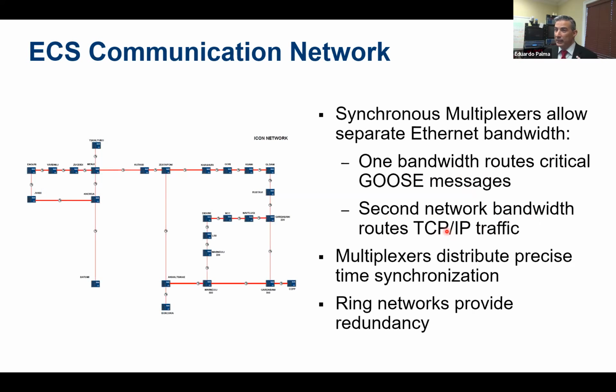Notice that on the physical network, or how these multiplexer boxes are connected to each other, there is one per substation, and they match the names of the 500 kV substations, and some are in 220 kV as well. But since the best type of redundancy comes when you connect the multiplexers in a ring topology, meaning in a closed loop, there are two paths, or redundant paths, in order for this information to get to its destination. So it increases the availability time as well.